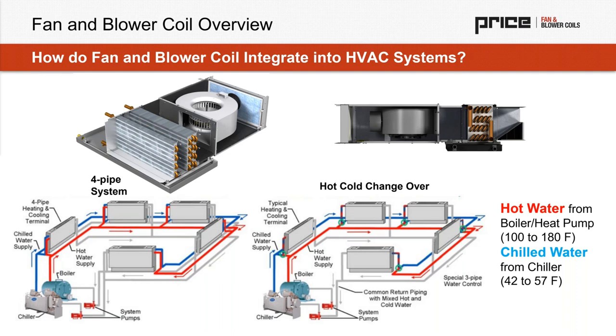On the left, we can see a very basic four-pipe system. We have a boiler and a chiller, both supplying water to a fan coil. This would be considered a four-pipe system, and therefore we're going to have a four-pipe fan coil. You can see the fan coil here has two different coils on the top left. We could have that heating coil positioned upstream of the cooling coil. That would be considered a preheat configuration, or we can flip the position of the two. We can have the coil that's providing heat in a downstream position, which would be a reheat application.